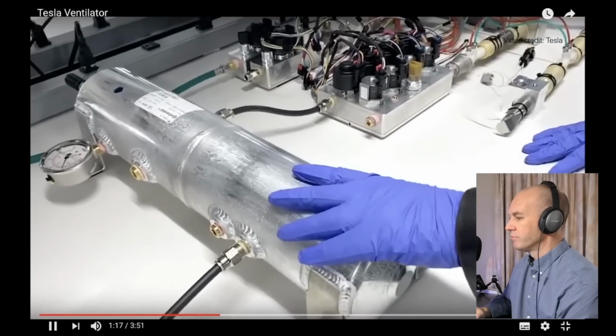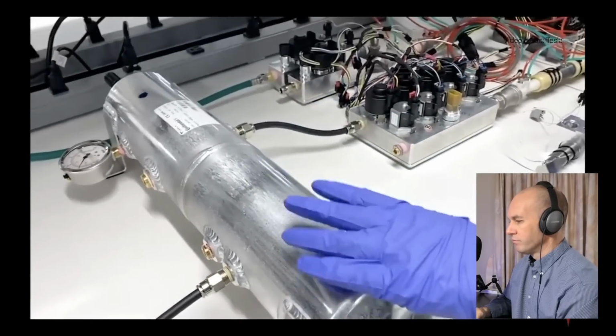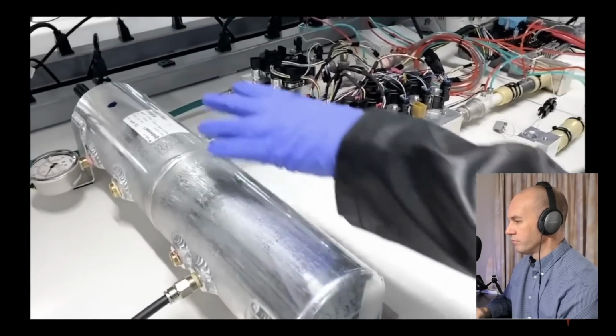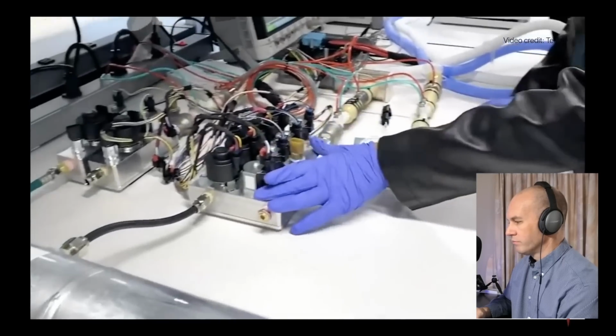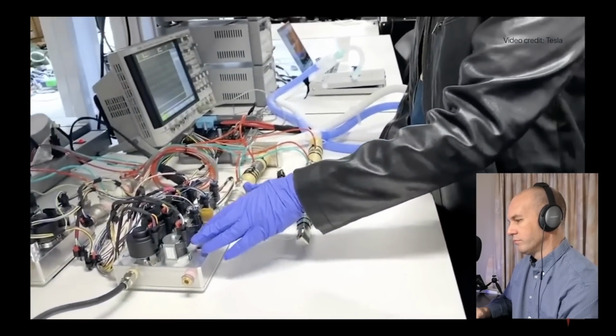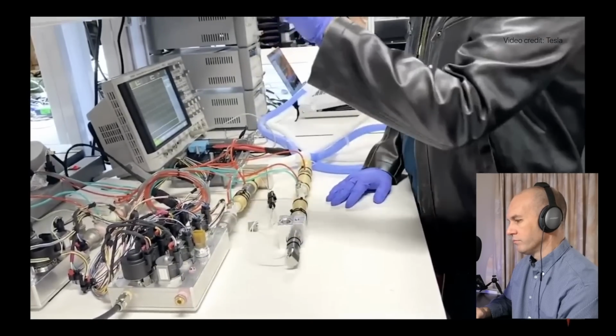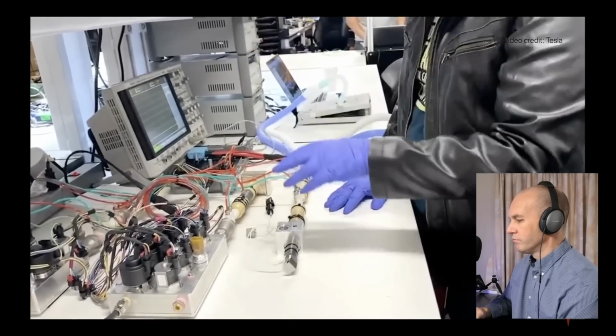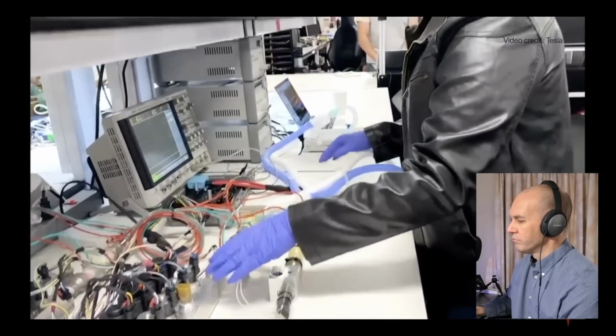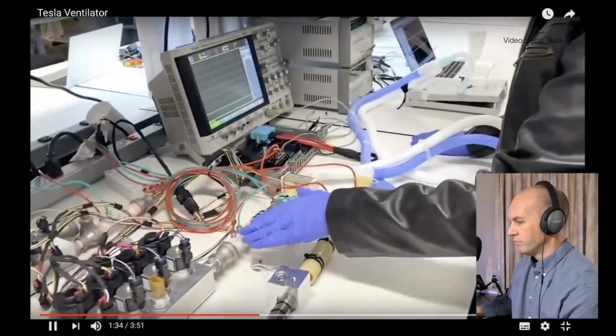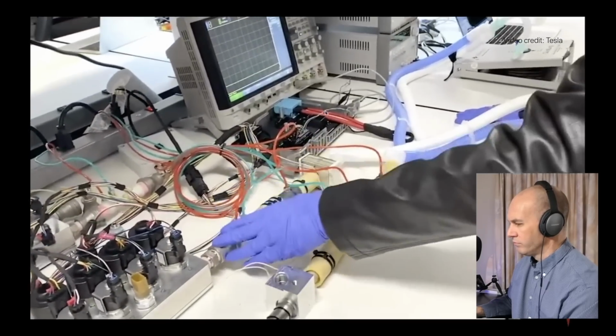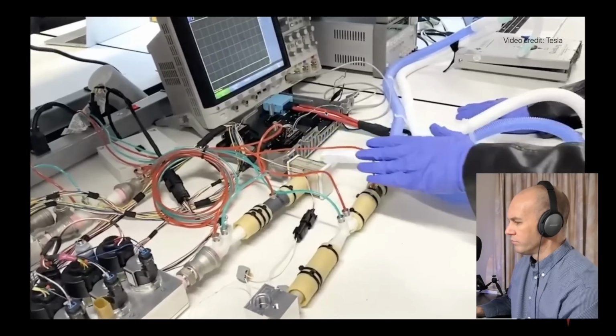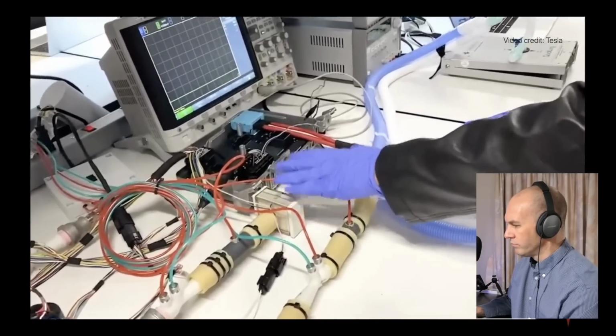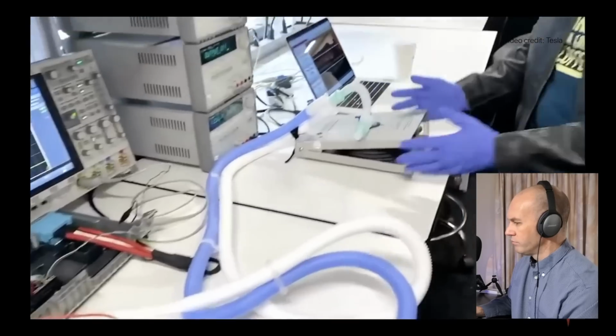In our vehicles, this is where the oxygen and the air mixes together, and then it passes through a valve body, which is used to create the waveforms, the pressure and the volume waveforms. Then the air coming out of this valve body goes to a bunch of sensors. So this is a flow rate sensor, this is a pressure sensor. It then goes through a filter and goes into the patient's lung.